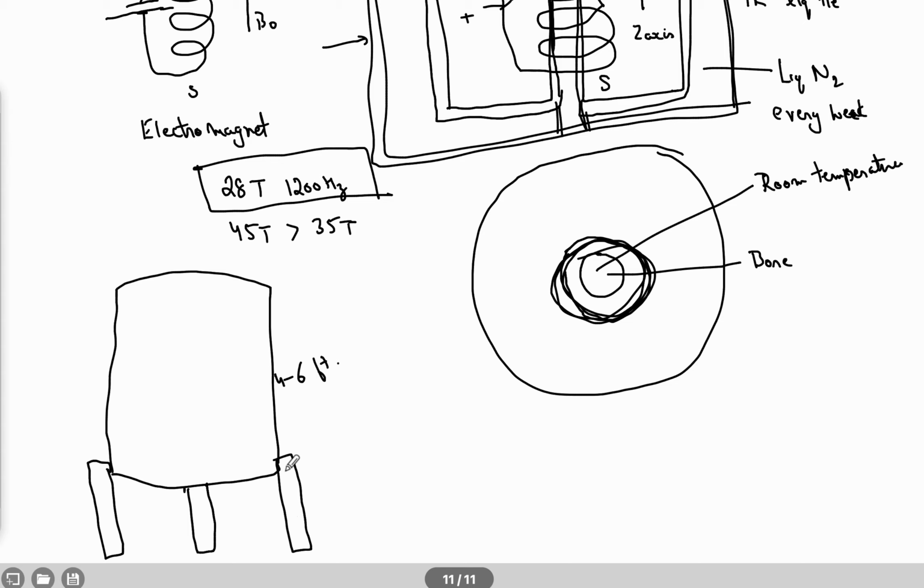So the legs have a special architecture where they filter out any kind of floor vibrations happening around the magnet. So through the floor, these vibrations should not pass. Whenever they come and install the magnet, they will test the floor for vibrations, what kind of vibrations are present in that room, so that the legs can be designed accordingly.